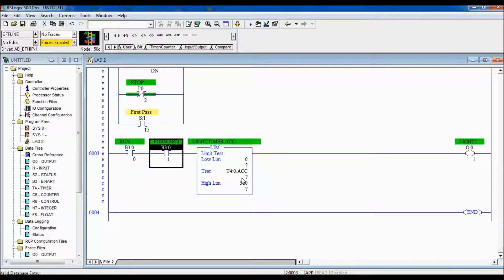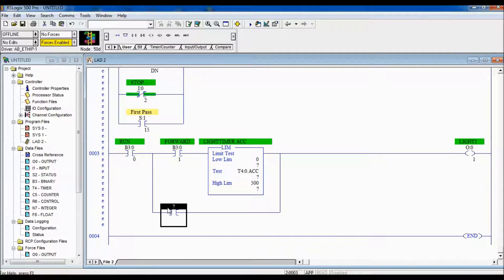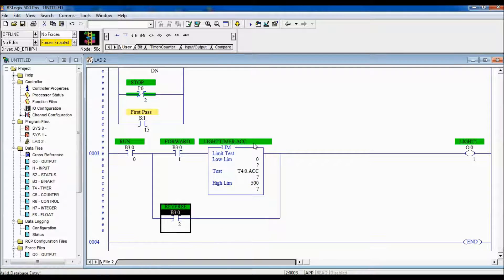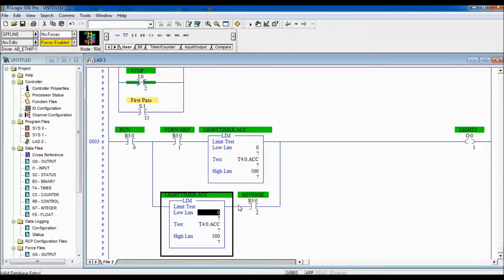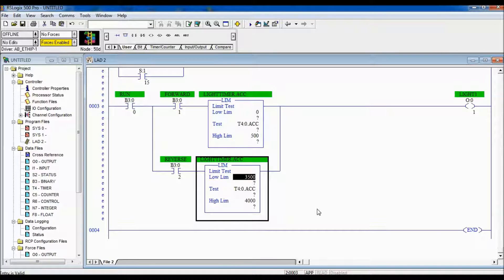Now let's also do the logic for when it's in reverse. If it's in reverse, we're going to grab a bit called 'reverse', stored at B3 colon zero slash two. We're going to use the same timer for both. For the reverse, our low limit is going to be 3,500 and our high limit is going to be 4,000 — so it's going the opposite way around the clock.